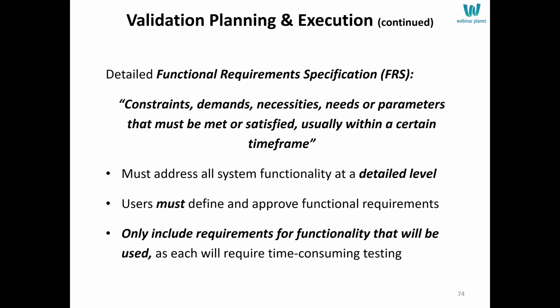Only include requirements for functionality that you're going to use. If you get a package and part of it you're not going to ever use, don't include that function or feature in your validation, because you're not going to use it. And then in your validation plan, you would specify that you ignored those particular functions or features because you're not going to use them. That's why you didn't include them in validation.